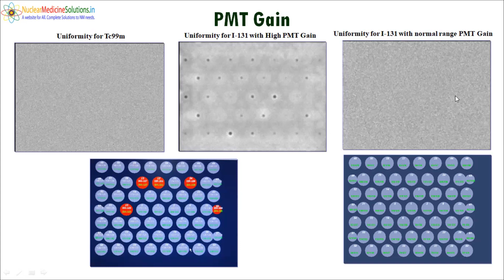We are creating different correction maps, that is the uniformity correction map, linearity correction map, and energy correction map. I will discuss them one by one, and the importance of these correction maps and why we are creating them. First comes the uniformity correction map. As you know, in the gamma camera, some PMTs have a high gain and some have less gain. The PMT gains are not the same. Theoretically, they should remain the same so we can get the same counts from each PMT. But in practice, it is not. Some PMTs give high counts, some give less counts. So to make it the same, we give a correction factor to each PMT by creating a uniformity correction map. And because of this, we are getting the same counts from each PMT.